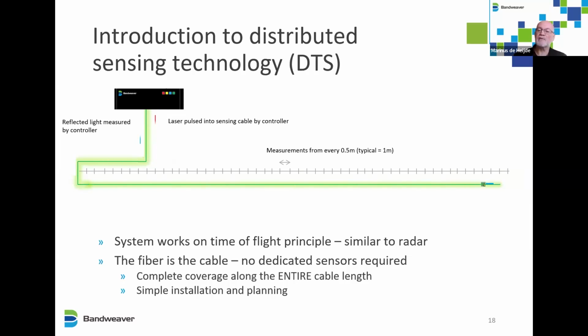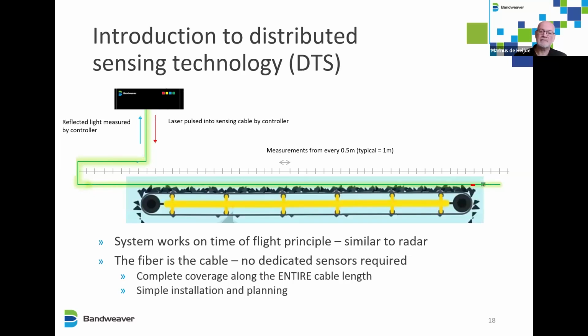The system works on a time of flight principle, if you're familiar with that, which is similar to radar. The main thing to remember is really that the fiber is the sensor. It's not the cable. We do not need any dedicated sensors. So there's complete coverage along the entire cable length, and it gives you very simple installation and planning. This shows you how it is next to a conveyor belt.